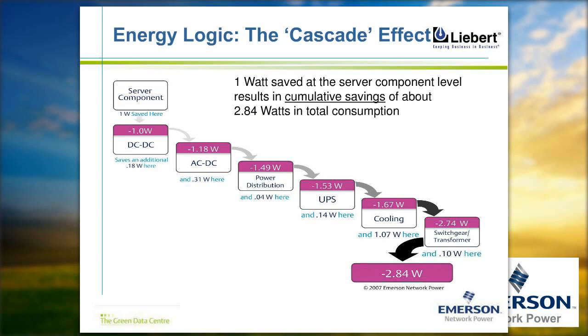Even if you look at rejecting the heat of, let's say, X kilowatt, we spend almost a similar kilowatt or more through the cooling system. So while you are selecting IT devices henceforth, see to it that you specify reduced IT consumption to get maximum computing. This is the message we would like to give through this cascade effect slide.